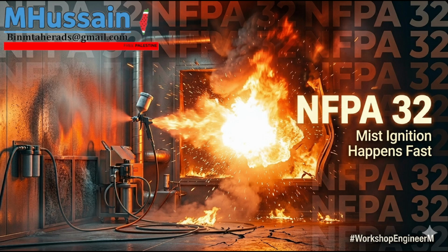Milliseconds. So you are not just designing an exhaust fan anymore. You are designing an autonomous life safety system with zero margin for latency. Right. The sensor calibration, the placement of the sniffers based on the specific gravity of the vapor, the fail-safe states of the relays, all of that falls squarely on the facility designer. That's a huge burden.